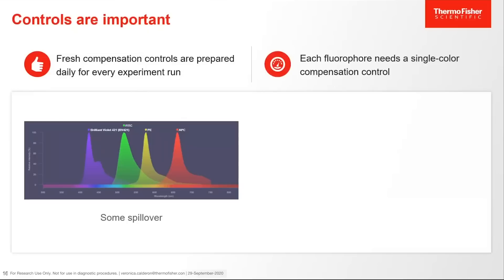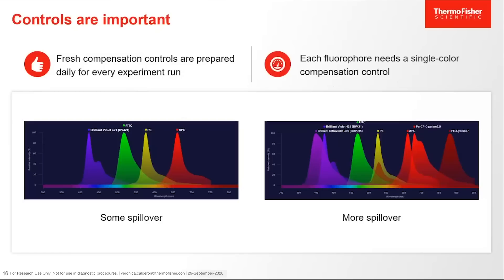Controls are important. Fresh compensation controls are prepared daily for each experimental run. There are day-to-day changes within your instrument's lasers that can occur, and light, temperature, and treatment changes can affect the performance of a fluorophore. Each fluorophore needs a single color compensation control. Whether doing a simple four-color panel or a more complex multicolor panel, spectral overlap will occur, and the spillover can affect the accuracy of the data.